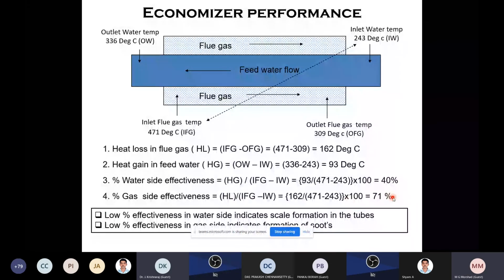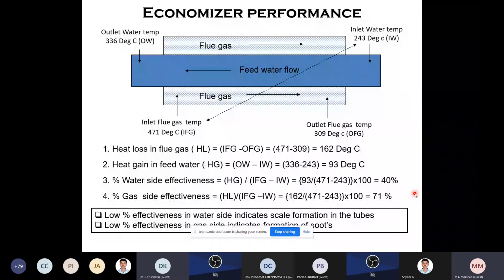So low effectiveness on the water side indicates scale formation in the tube, and low effectiveness on the gas side indicates soot formation. So by checking all these things, you can find out whether there is scale formation or soot formation. If the soot formation is there, you have to go for the soot blower to clean the soot.